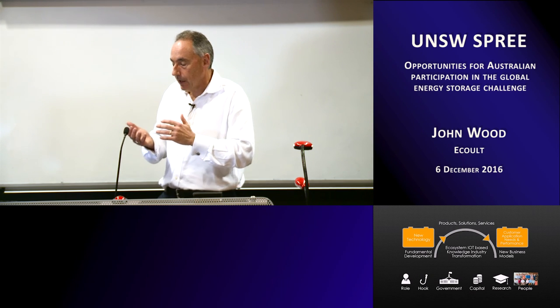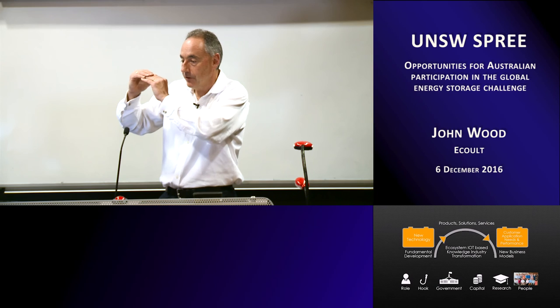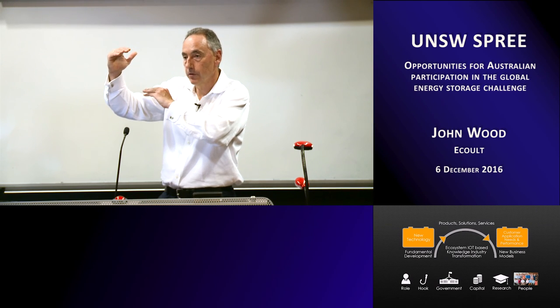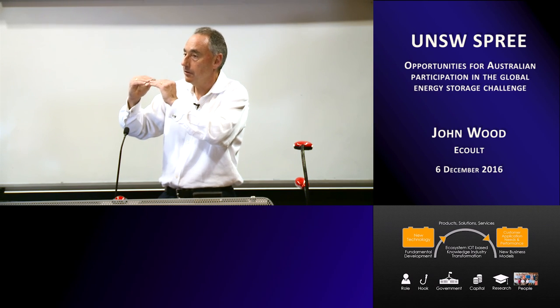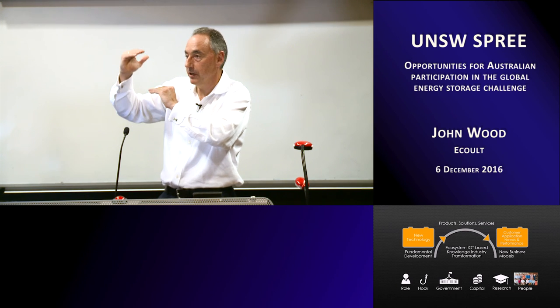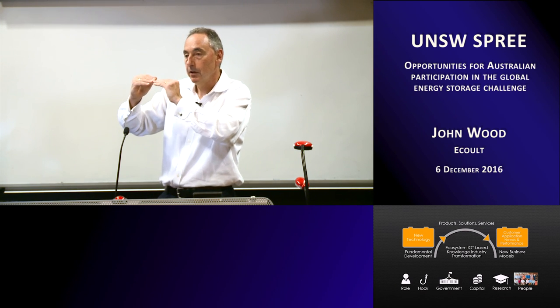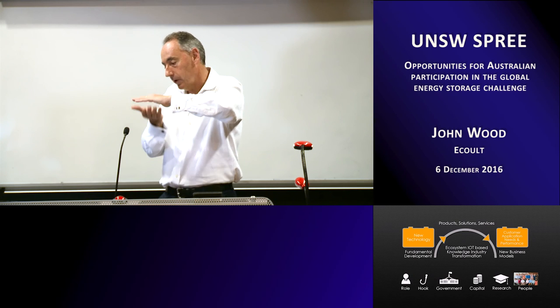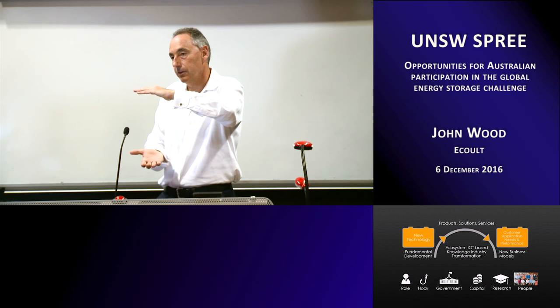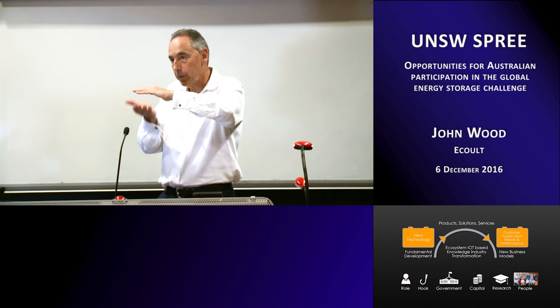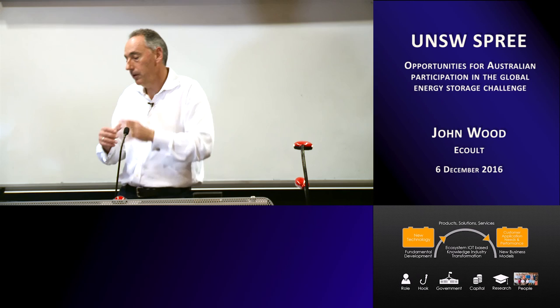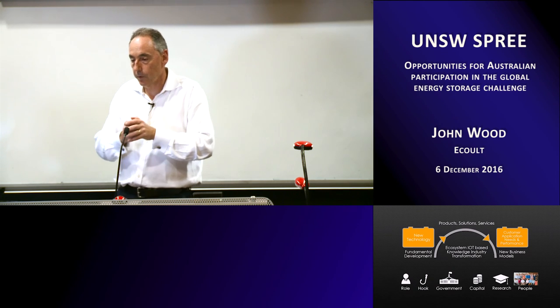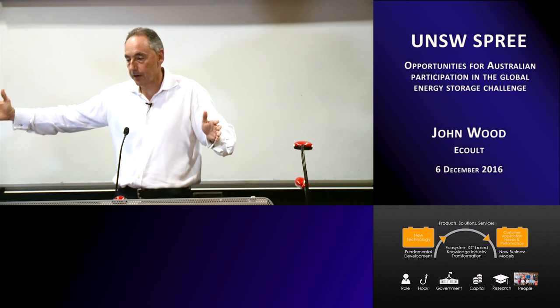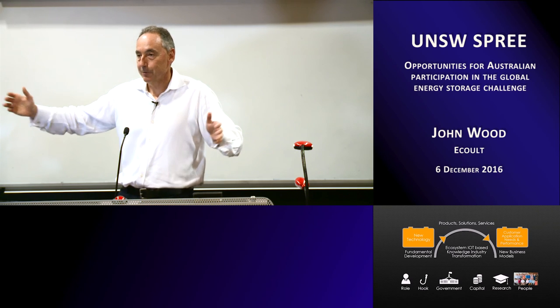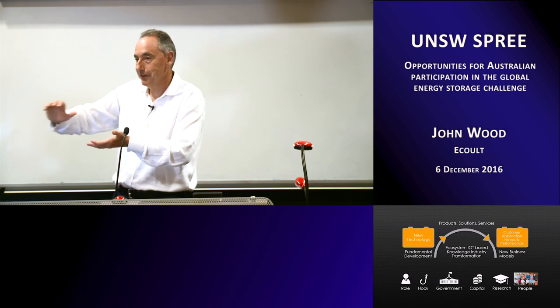That's it — they're a function of voltage and temperature. Now, lead acid traditionally has been held on float for reserve power, or in the case of gel batteries, held in that upper 20% of the range of charge. We operate in a partial state of charge, and because of that, the internal voltage of the battery is lower, so the operating voltage is lower. And so you can do the spreadsheet work: what's going to be my rate of degradation through positive grid corrosion given these voltages and these temperatures?